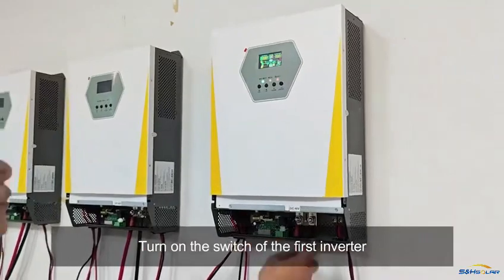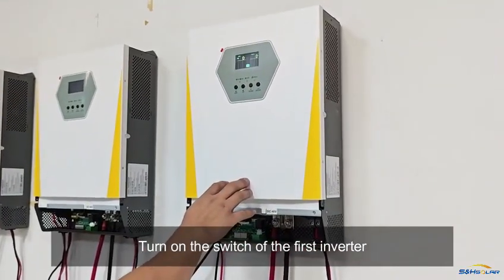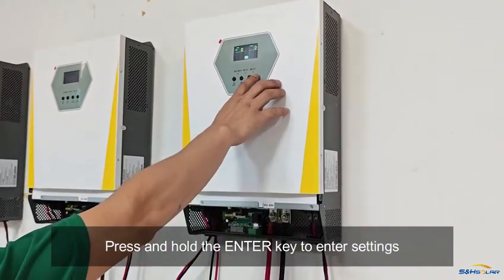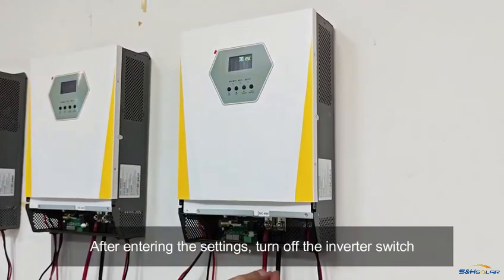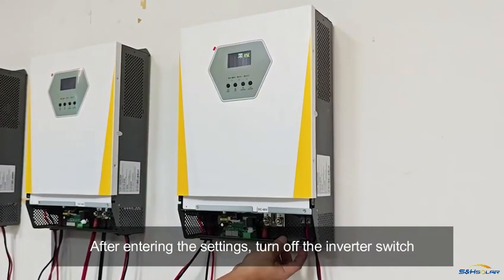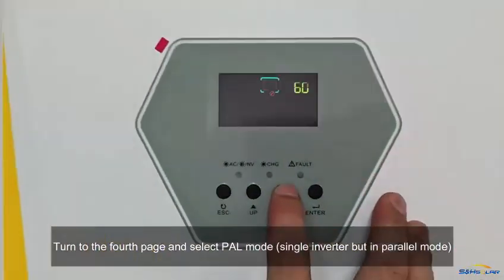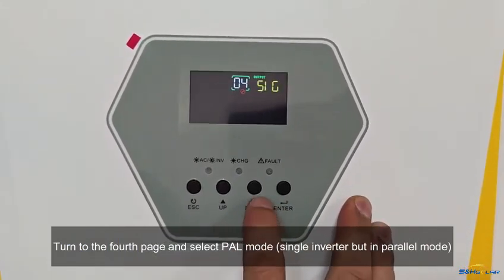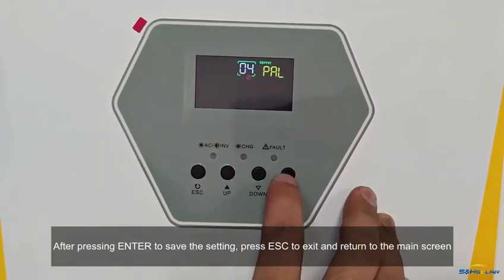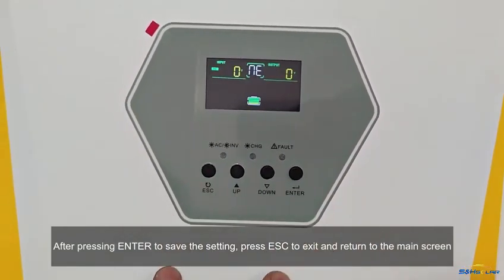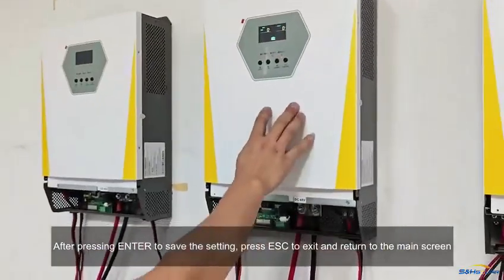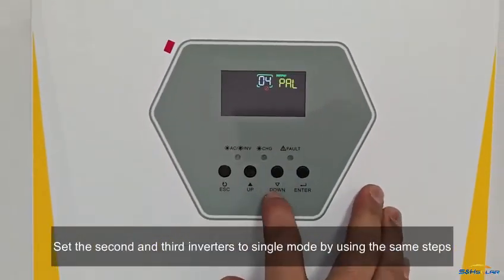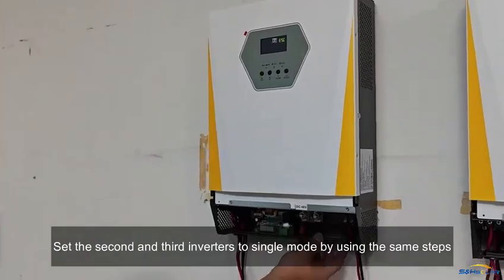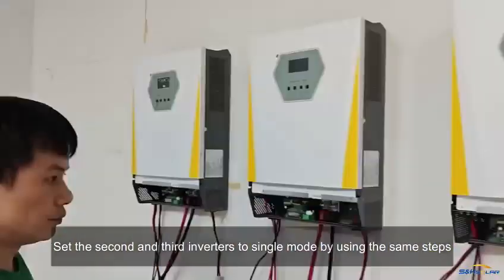Turn on the switch of the first inverter. Press and hold the enter key to enter settings. After entering the settings, turn off the inverter switch. Turn to the fourth page and select PAL mode, single inverter but in parallel mode. After pressing enter to save the setting, press ESC to exit and return to the main screen. Set the second and third inverters to single mode by using the same steps.